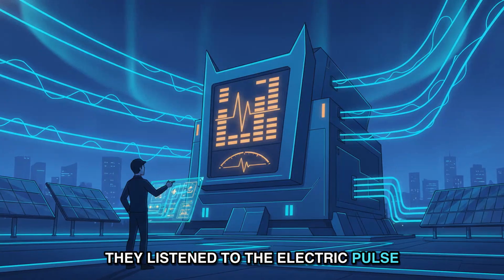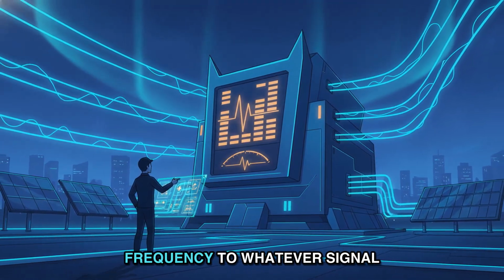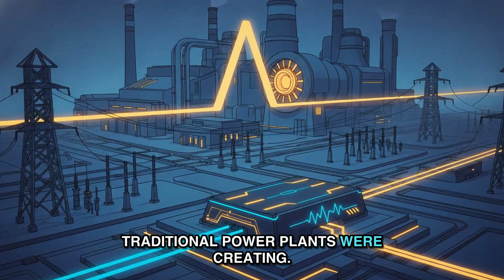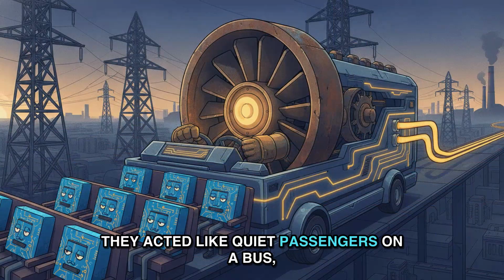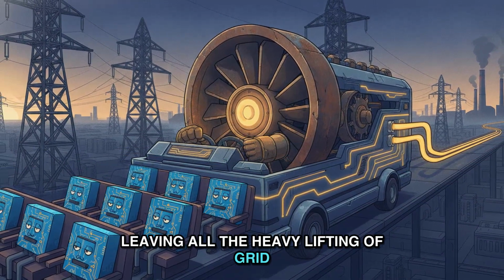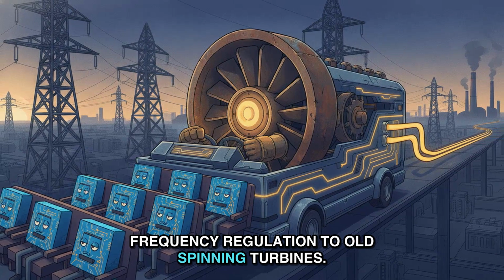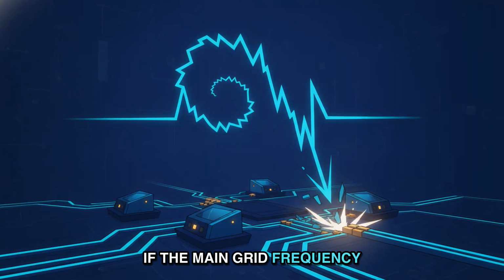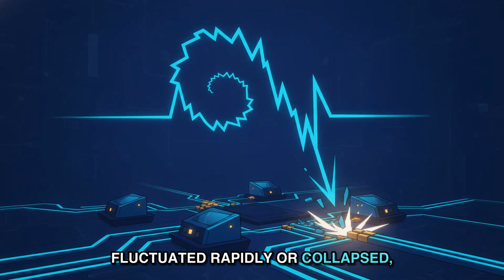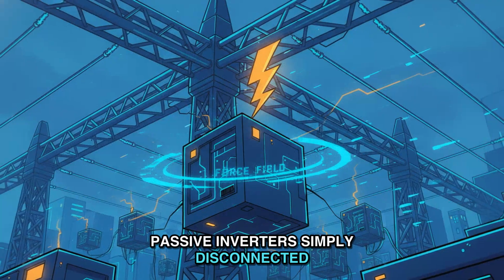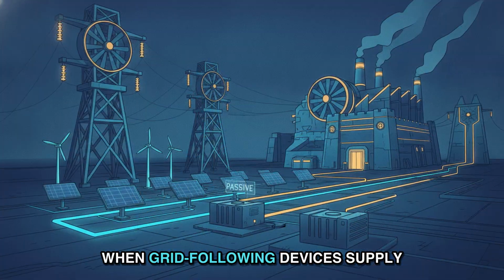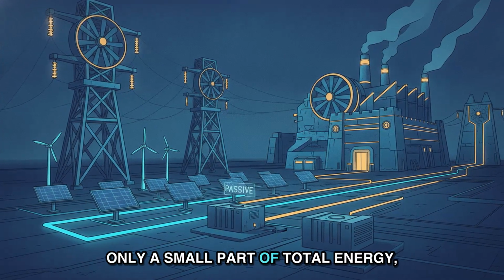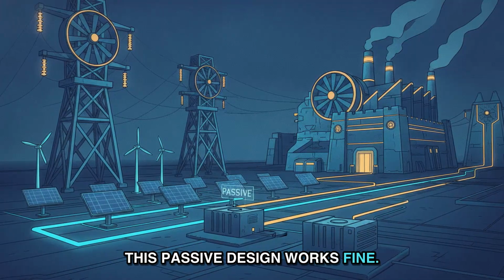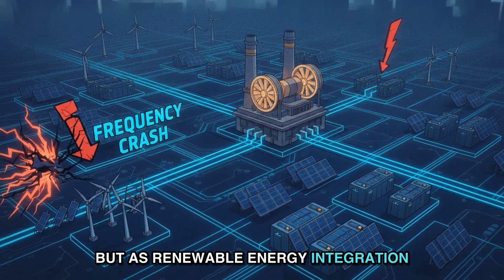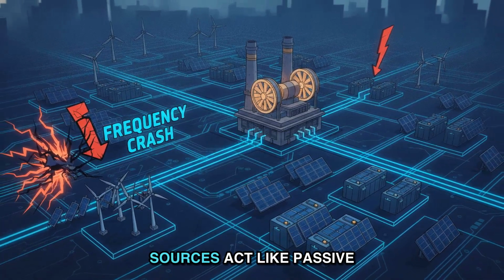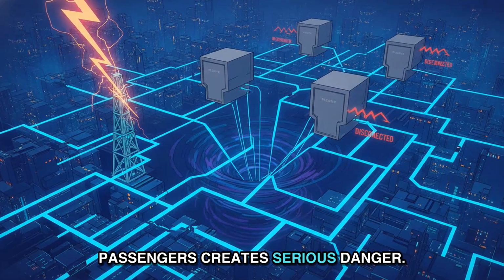They listened to the electric pulse of the grid and matched their output frequency to whatever signal traditional power plants were creating. They acted like quiet passengers on a bus, leaving all the heavy lifting of grid frequency regulation to old spinning turbines. If the main grid frequency fluctuated rapidly or collapsed, passive inverters simply disconnected themselves from the network. When grid-following devices supply only a small part of total energy, this passive design works fine. But as renewable energy integration reaches high levels, having most power sources act like passive passengers creates serious danger.